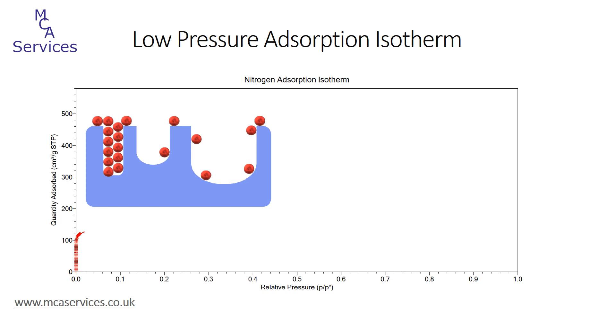In the representation of our sample, nitrogen is shown as red spheres, and we can see that the isotherm to a point roughly corresponding to this stage is shown as the red line on the plot below. Note that the x-axis scale is shown as relative pressure, which is quite normal for gas adsorption isotherms — it's the absolute pressure dosed to the sample analysis tube relative to the saturation vapour pressure of the adsorbate. In the case of nitrogen, the saturation vapour pressure will be measured as part of the analysis and will tend to be slightly higher than atmospheric pressure.